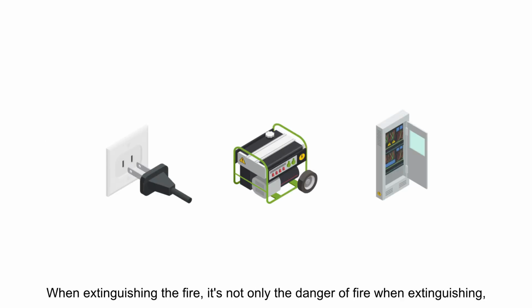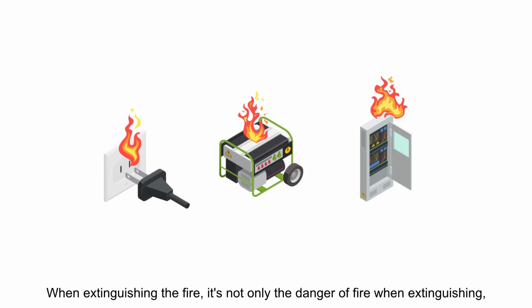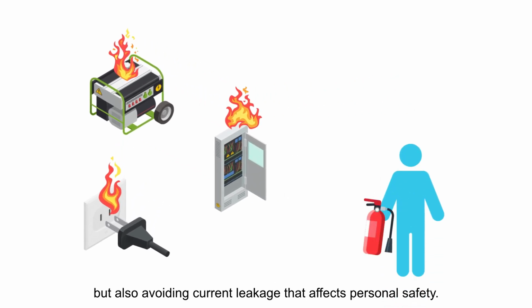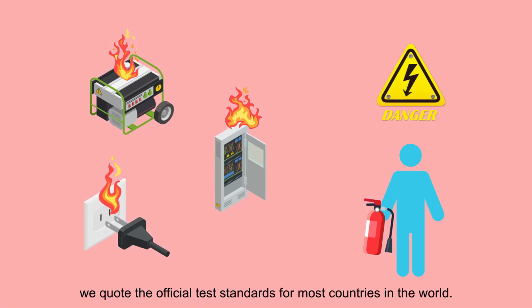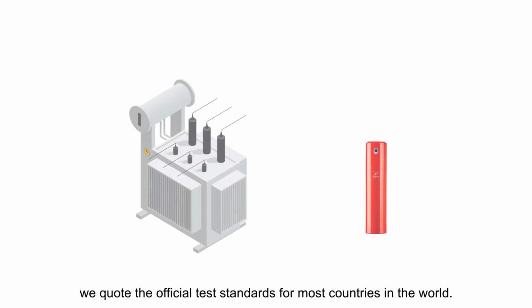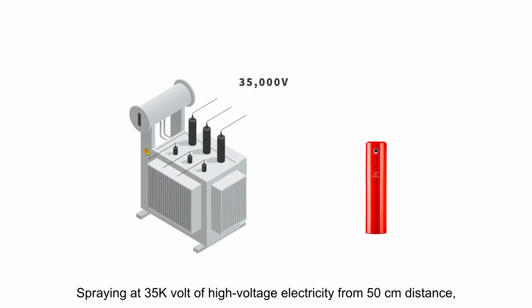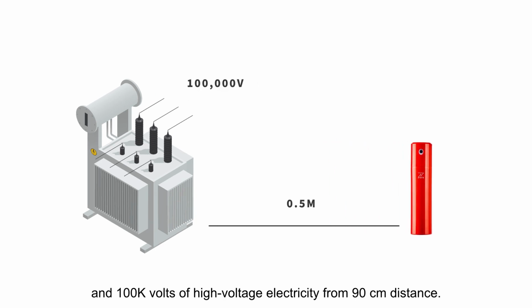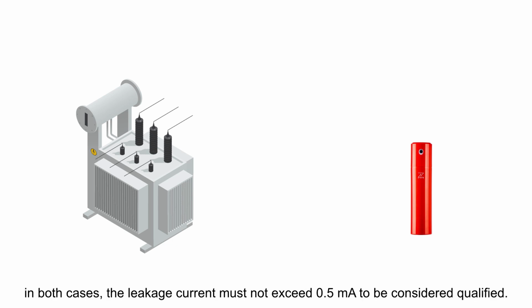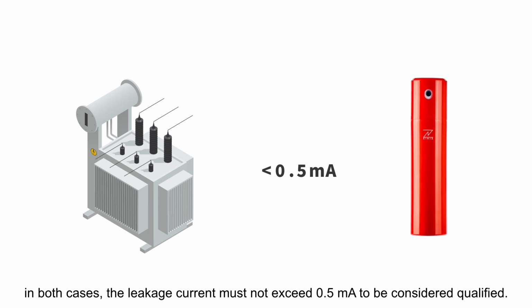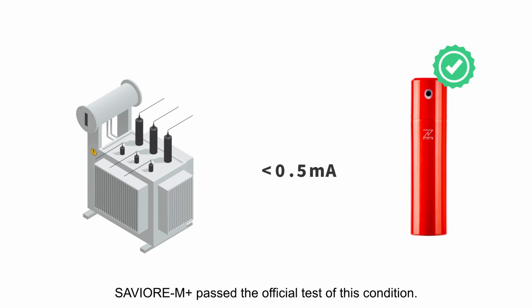Electrical equipment fire is fire on an energized object. When extinguishing, there is not only the danger of fire, but also the need to avoid current leakage that affects personal safety. Because the current cannot be filmed, we quote the official test standards used by most countries in the world. Spraying at 35,000 volts of high voltage electricity from 50 centimeters distance, and 100,000 volts from 90 centimeters distance. In both cases, the leakage current must not exceed 0.5 milliamps to be considered qualified. SAVIORE-M Plus passed the official test of this condition.